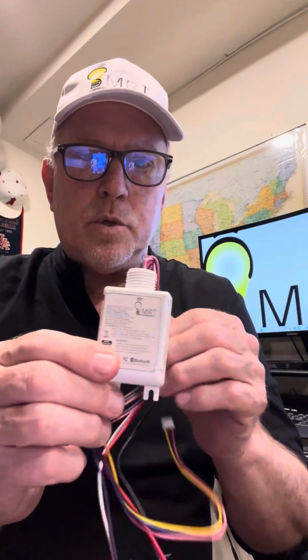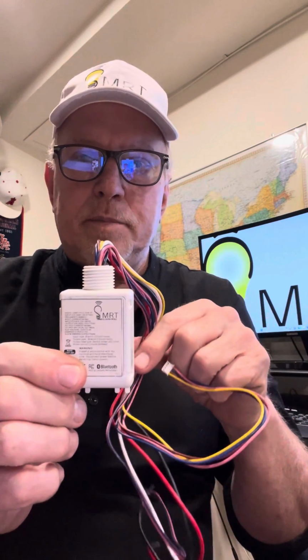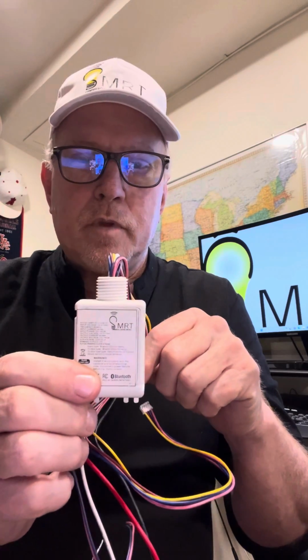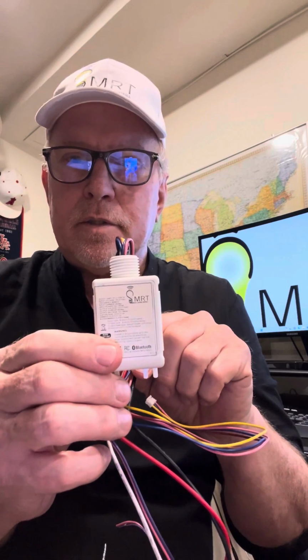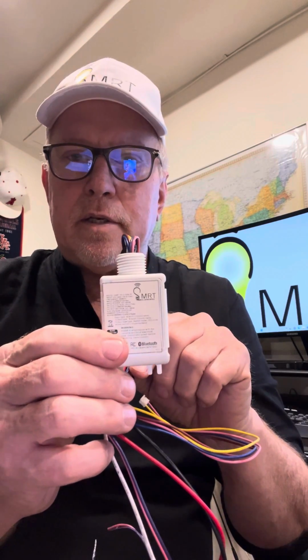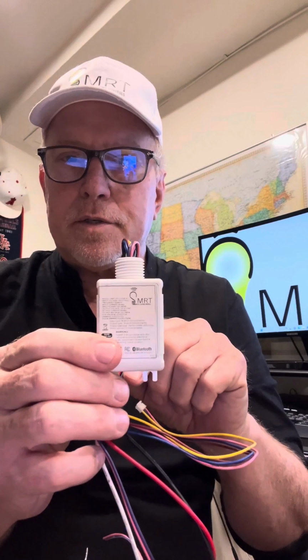At 120 volts times 10 amps, that would be 1200 watts, but we don't want to overload this, so we're going to derate it and not put any more than 960 watts on this power pack. That's a 20% derating. This is going to be set up and controlled by our Bluetooth app. It's wired to your different fixtures and gives you the ability to dim a whole series of fixtures with this one little power pack. So this is the computer brain. This is where it all starts.